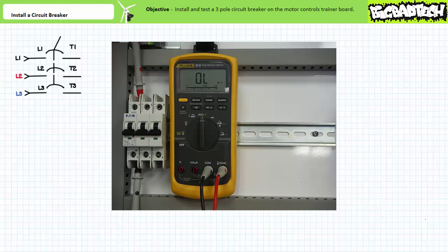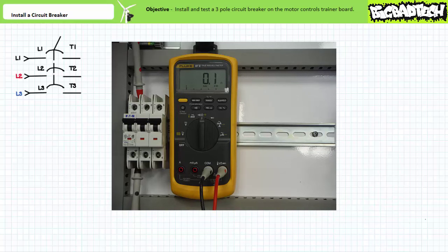First we'll test the basic operation of the circuit breaker. When the manual switch is pulled down the ohmmeter indicates the circuit breaker L to T contacts are open. When the manual switch is pushed up the ohmmeter indicates the circuit breaker L to T primary contacts are closed.